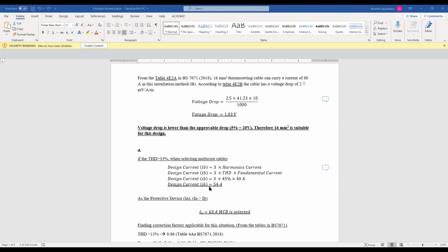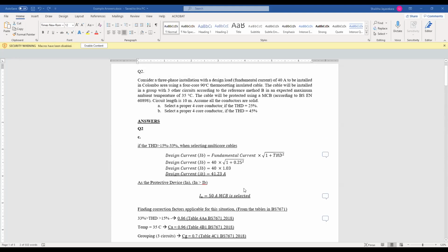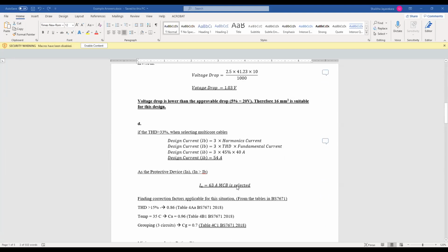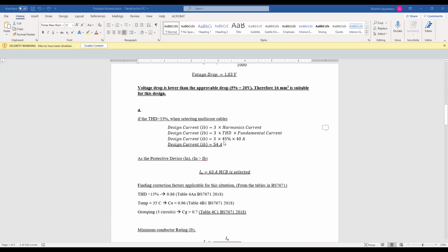So in here your current is 54 amperes. It will become 54 amperes. So earlier, see the design, the fundamental is only 40 amperes. So in here our design current was 41.23 after adding this THD value also. But in here our current is much higher in the neutral. So this is only the neutral current. So in the phase current it is not this much higher. So neutral current will be higher.